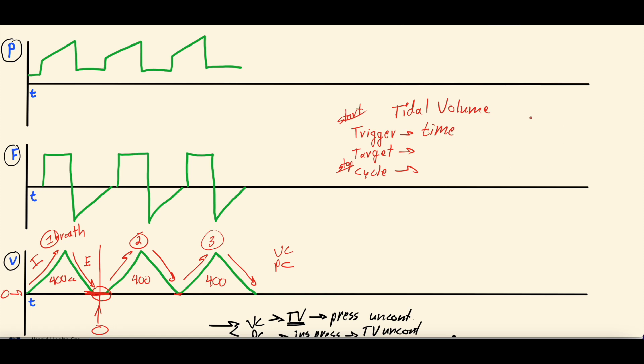The trigger is time because we set a respiratory rate. If we set the rate at 20, that means every 60 seconds the patient needs 20 breaths — about one breath every three seconds. This is assist control, meaning the patient can also take their own breaths, and those count toward the 20. But if the patient is not taking their own breaths, every three seconds the ventilator triggers itself to give a breath.